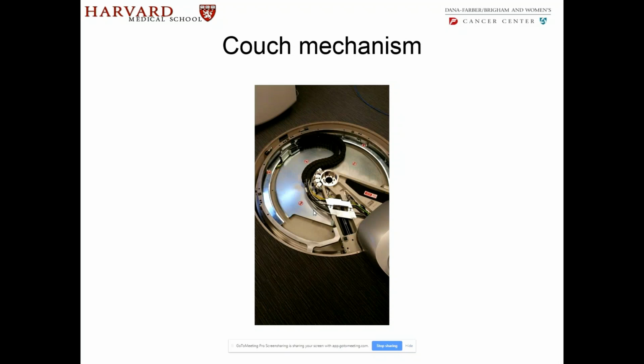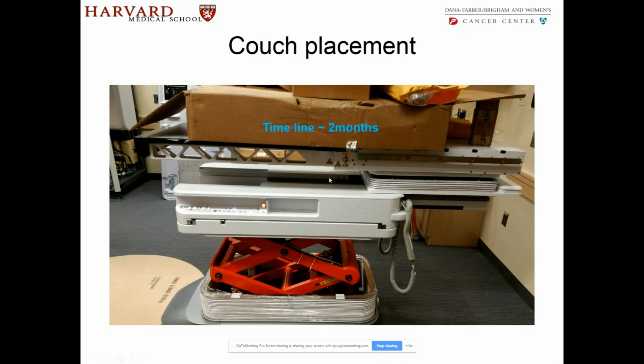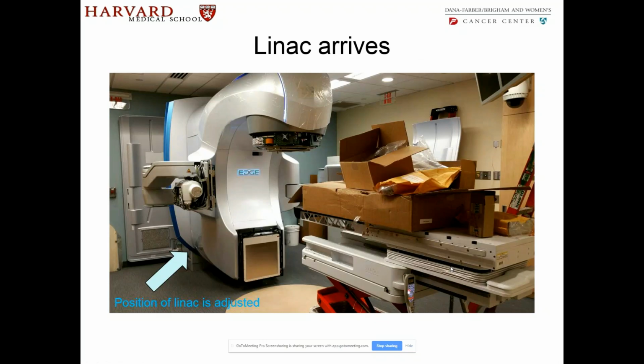So this is the couch mechanism. This is the axis around which the couch would rotate from the center. Usually, it takes about 2 months between the couch placement and the Linac being placed. So the couch mechanism, the couch, is placed. You see, this was the circular region which has been covered. Now, of course, the construction has gone on and the carpet has been placed. The Linac comes in. When you place the Linac, the position of the Linac is adjusted to match the ISO center of the Linac with that of the couch. It's not the other way around.